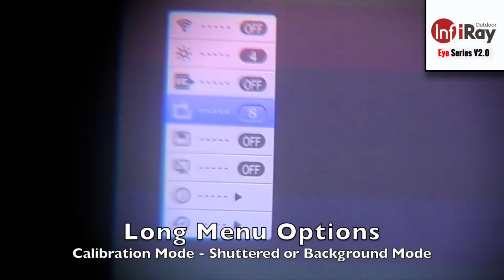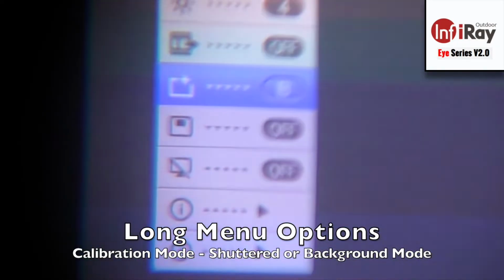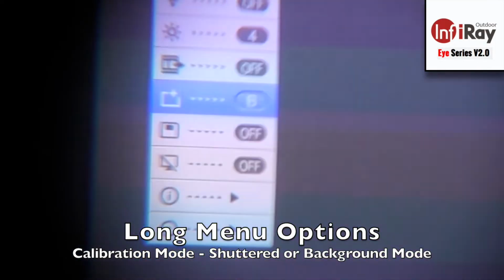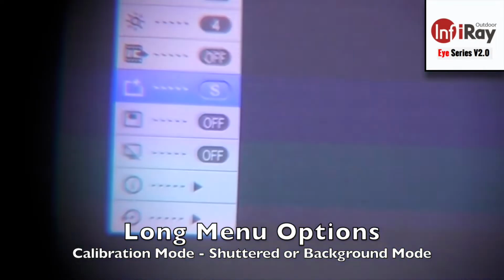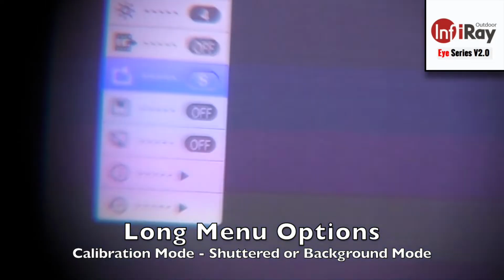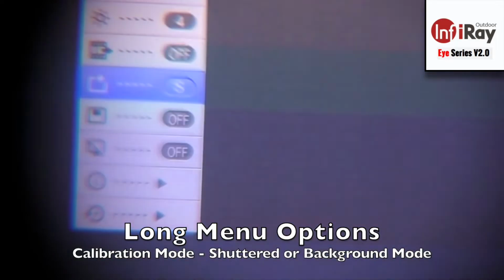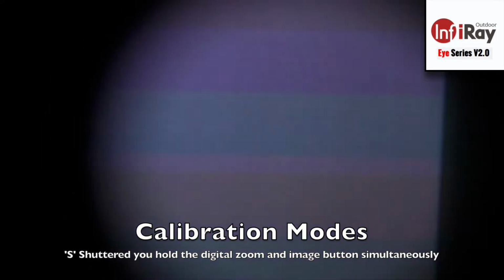Next icon down is going to be your calibration mode. You have shuttered, which is S, or B for background. The B selection is going to require you to cover the lens cap, whereas S is going to run auto, so you won't have to use the lens cap when a calibration is performed. Let's leave it in S for now. Let this time out. In order to calibrate the unit at any given time manually, you're going to press and hold the digital magnification button and image capture button for 2 seconds simultaneously. Right there, I heard the shutter calibrate the unit.